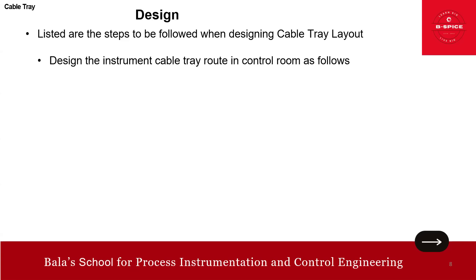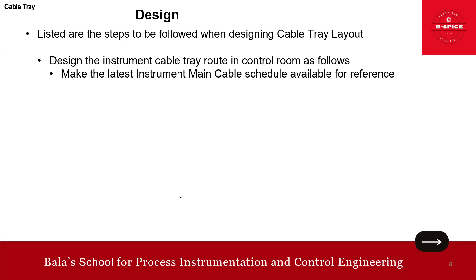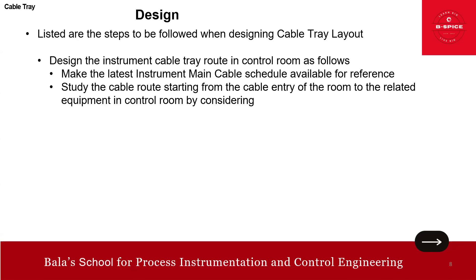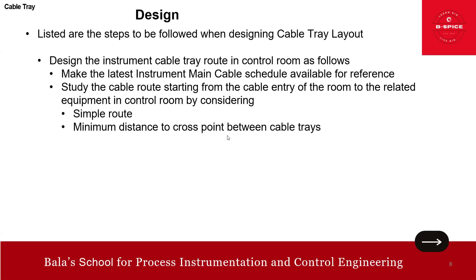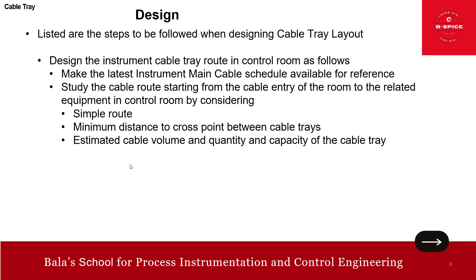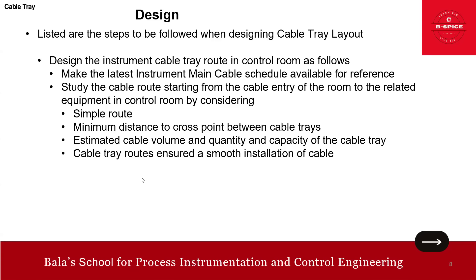When designing the cable tray route in the control room: first, make the latest instrument cable schedule available - this determines how many cables and how many trays are needed. Then study the cable route starting from the cable entry of the room to the related equipment in the control room, considering a simple, straight route - not zigzag - with minimum cross points between cable trays. Also estimate cable volume, quantity, and capacity of the cable tray.